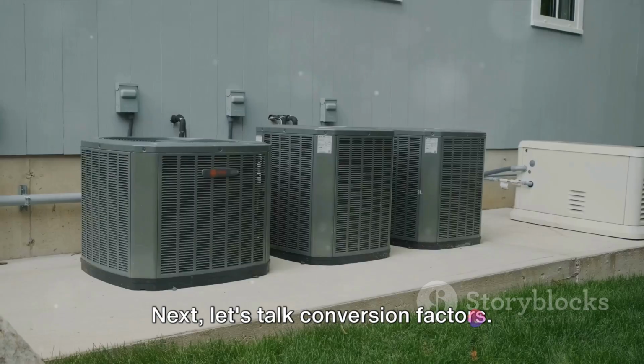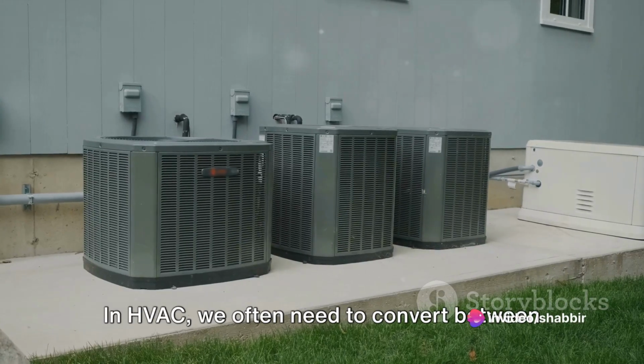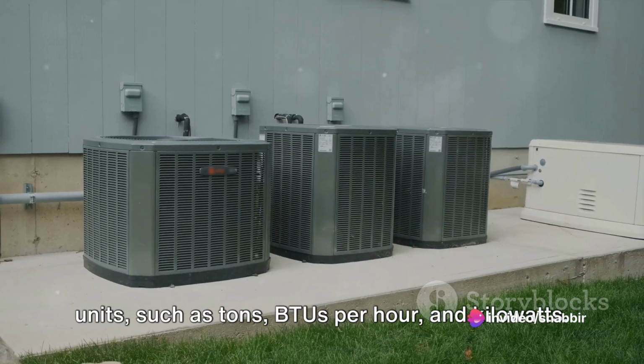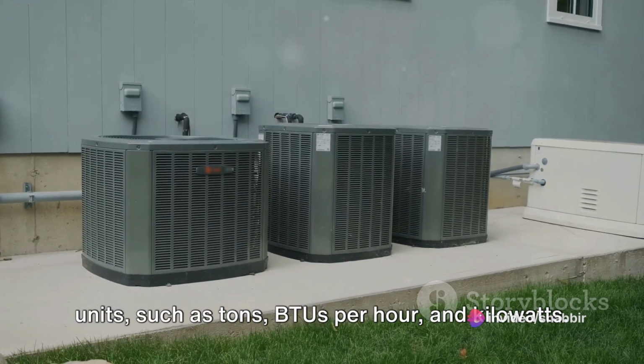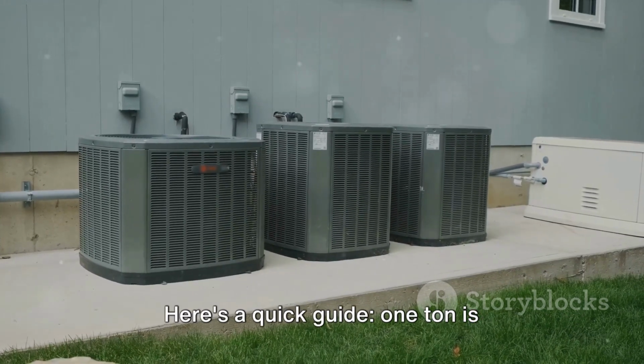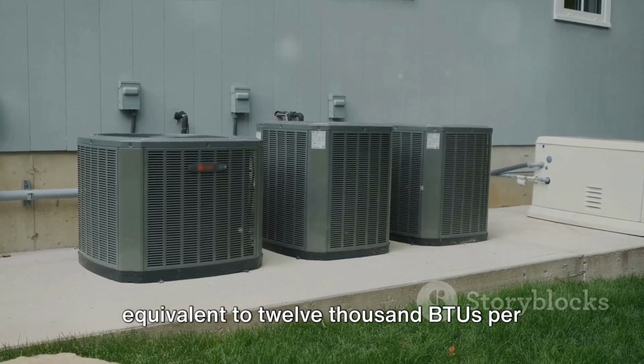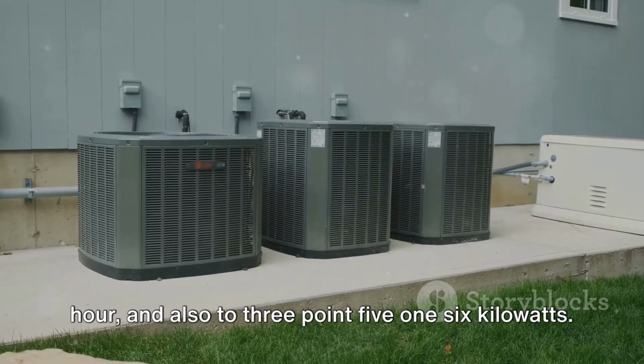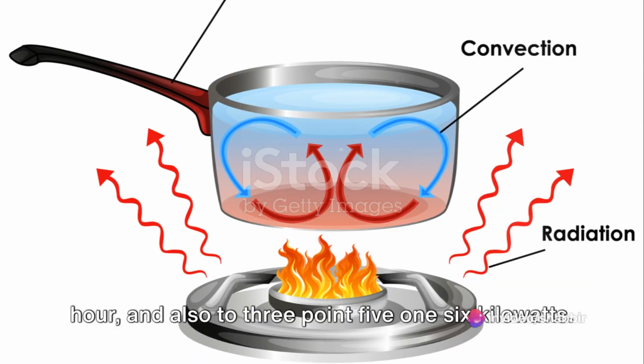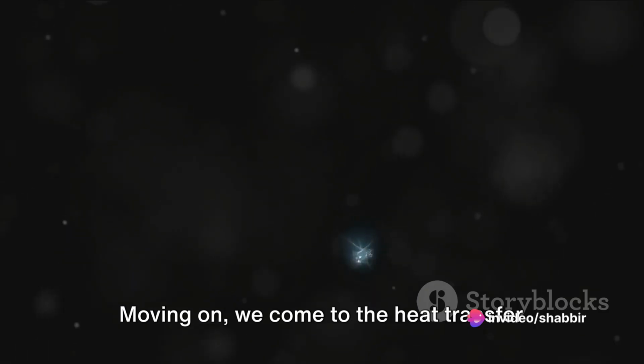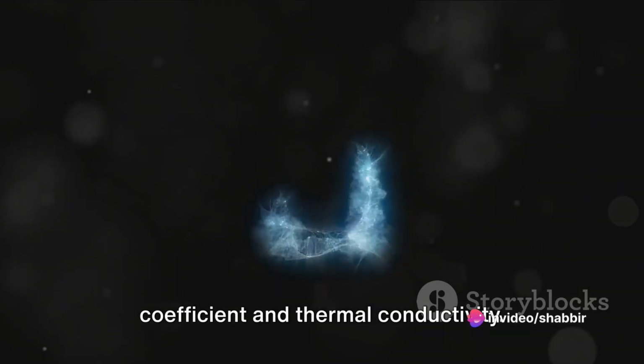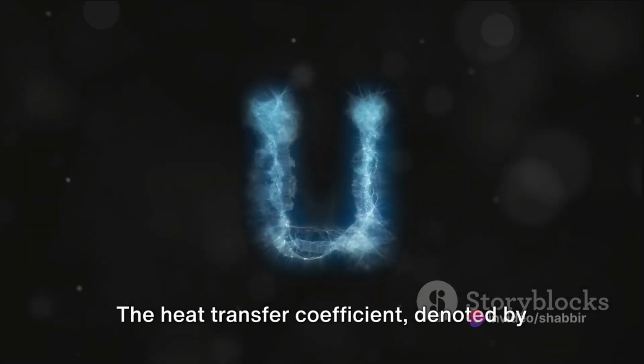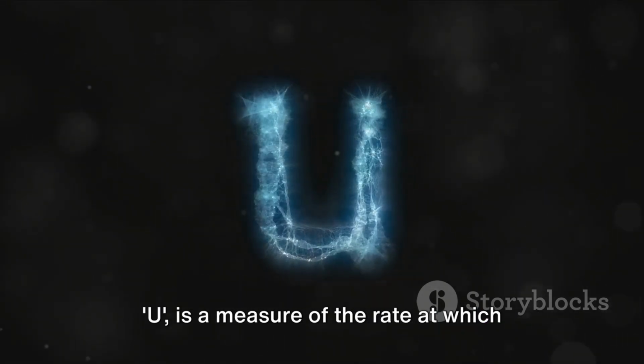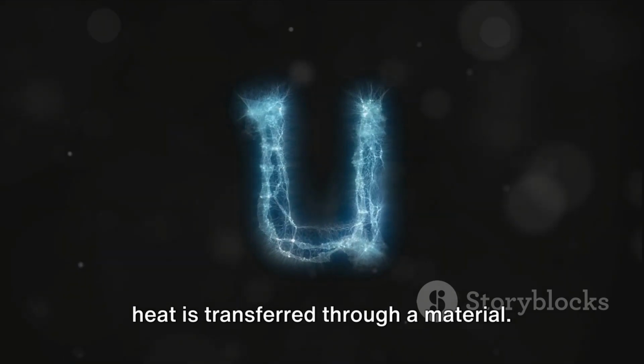Next, let's talk conversion factors. In HVAC, we often need to convert between units such as tons, BTUs per hour, and kilowatts. Here's a quick guide. 1 ton is equivalent to 12,000 BTUs per hour, and also to 3.516 kilowatts. Moving on, we come to the heat transfer coefficient and thermal conductivity. The heat transfer coefficient, denoted by U, is a measure of the rate at which heat is transferred through a material.